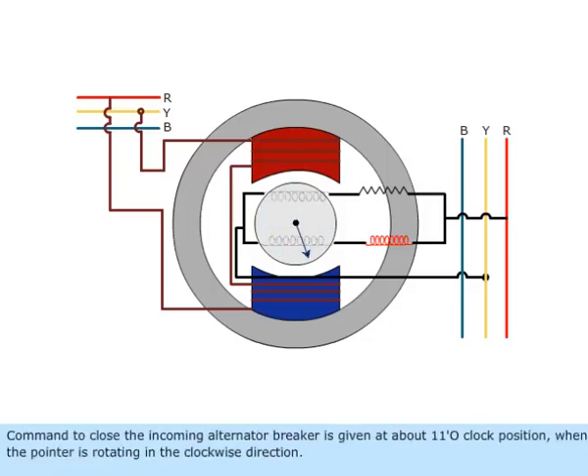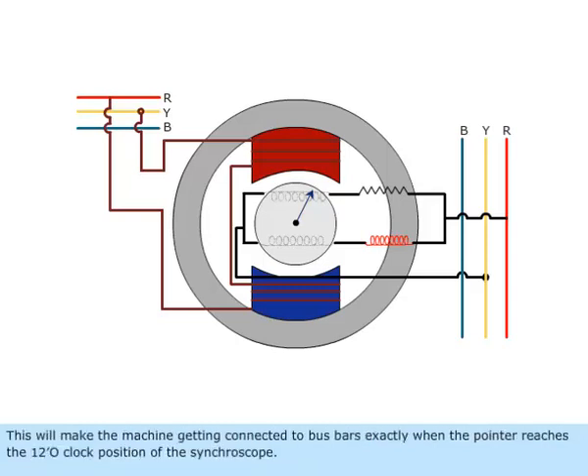The command to close the incoming alternator breaker is given at about 11 o'clock position when the pointer is rotating in the clockwise direction. This will make the machine getting connected to busbars exactly when the pointer reaches the 12 o'clock position of the synchroscope.